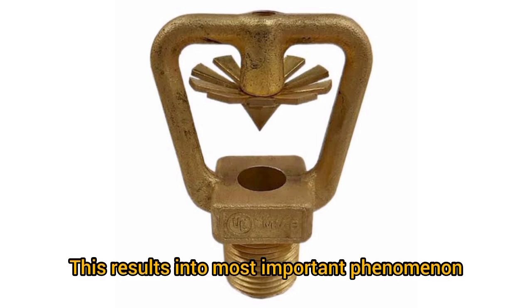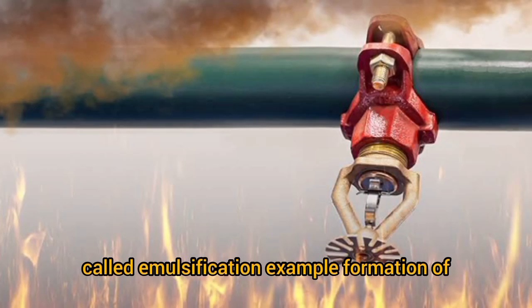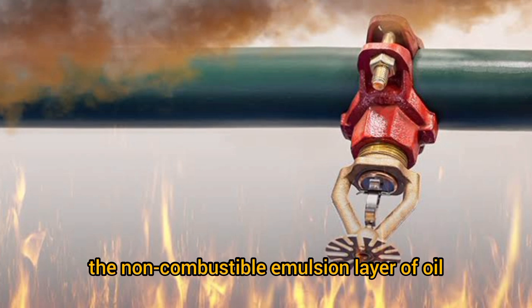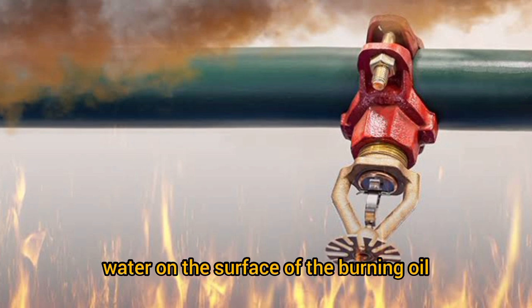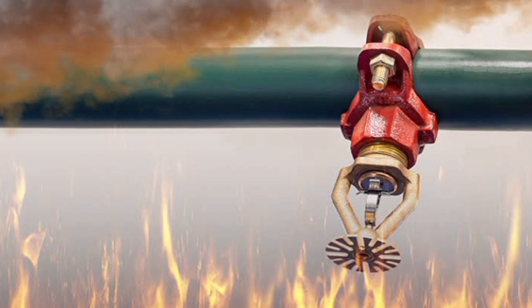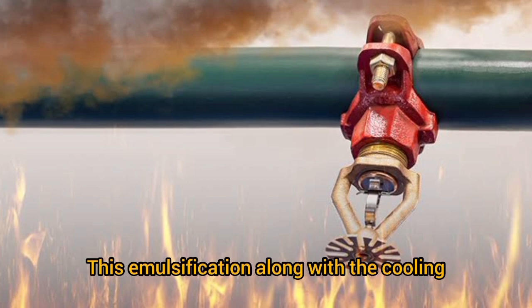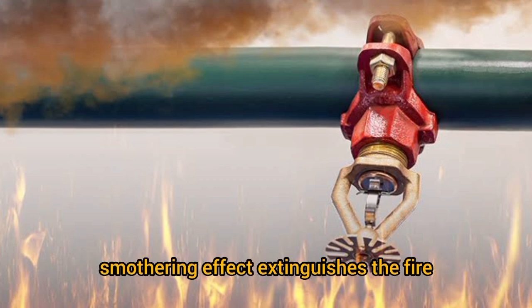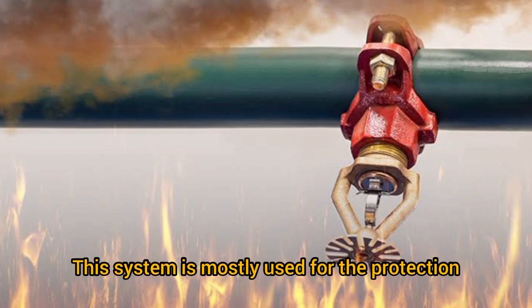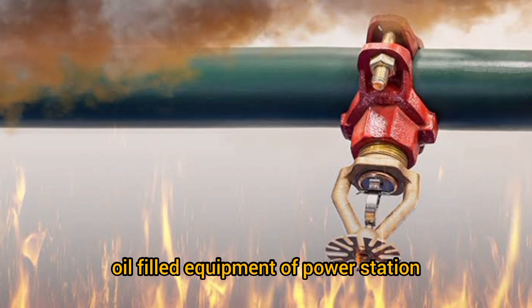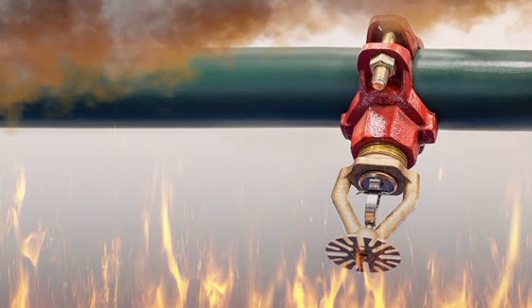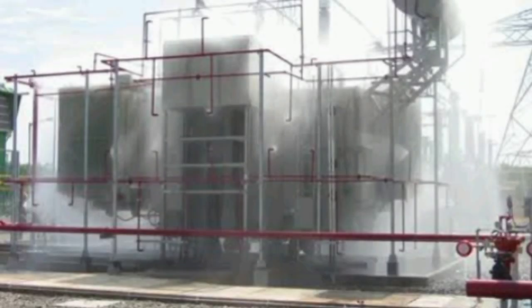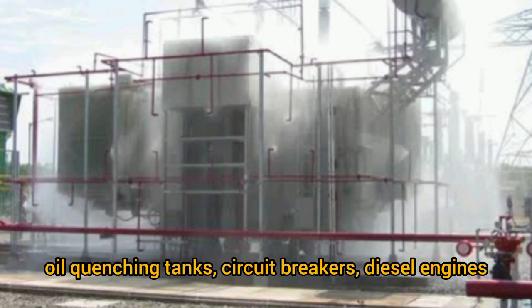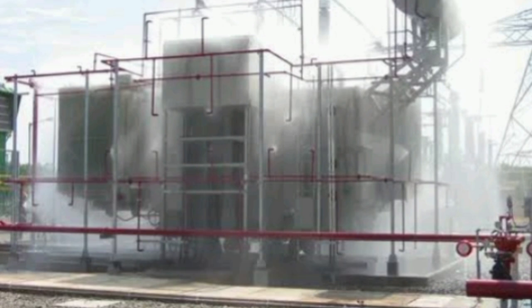This results in the most important phenomenon called emulsification. Example: formation of a non-combustible emulsion layer of oil and water on the surface of the burning oil. This emulsification along with the cooling and smothering effect extinguishes the fire. This system is mostly used for the protection of the following: transformer, oil-filled equipment of power station, turbo alternator lube oil system, oil-filled boiler room, oil quenching tanks, circuit breakers, diesel engines, fuel oil storage tanks.